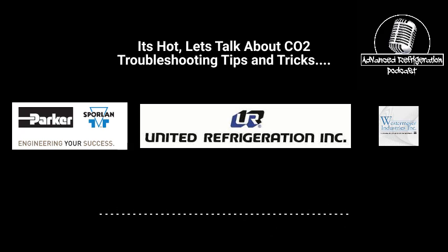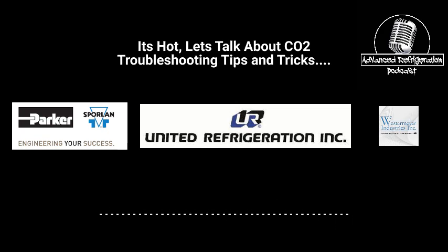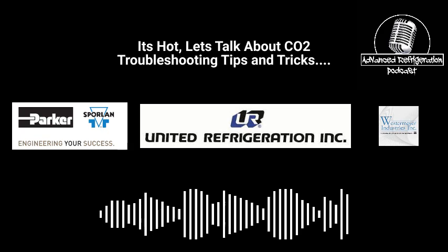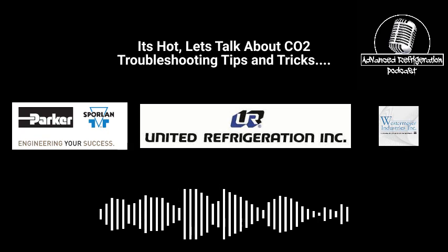So did anybody check the subcooling number? The subcooling number was 5, or 3. So it was reading like 5 or 3 degrees of subcooling? No, I don't know what it was reading. I just know what the set point is. If you go in and hold one of the program settings, it's in one of the U settings. I don't remember which U it is without looking at the manual, but it'll tell you what the actual subcooling readout is.